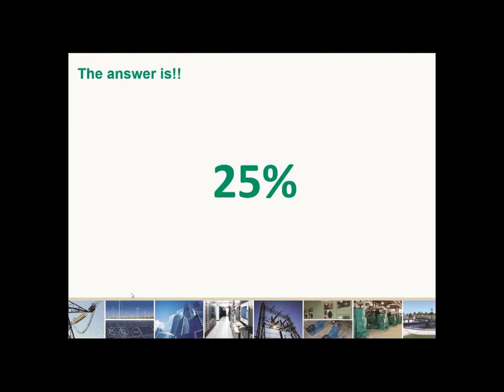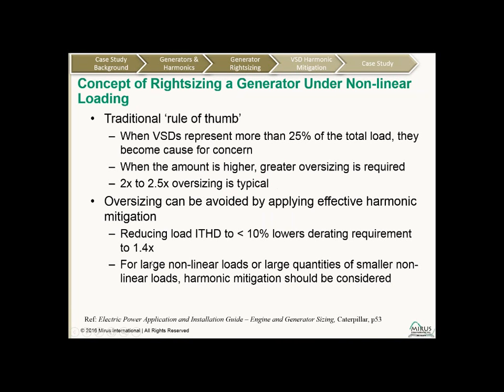Okay, so here are the answers. We've got about 19% that think it's only 25% of nonlinear loading. Another 35% believe it's at 50% nonlinear loading, 10% at 75%, and 13% at full load. And a few of you have no idea. Hopefully by the end of this presentation, you will have some idea. So the actual answer is 25%. So it doesn't take very much nonlinear load for the generator manufacturers to recommend that it be oversized.